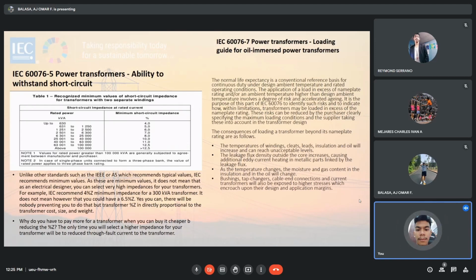Pwede siya, depende sa kung paano mo siya di-design. Dito sa IEC is, nag-recommend lang sila ng mga minimum values. So, why do you have to pay for a transformer? We can buy it cheaper, reducing the impedance. The only time you will select a higher impedance for your transformer will be to reduce through-fault current to the transformer. Dito sa IEC 60076-7, Power Transformers, Loading Guide for Oil Immersed Transformers.